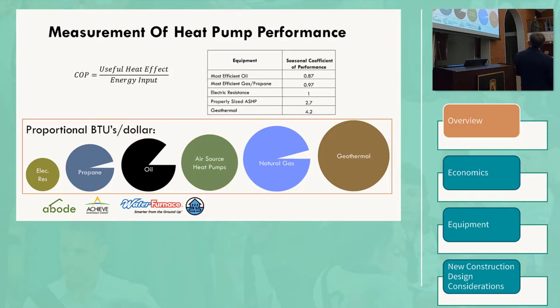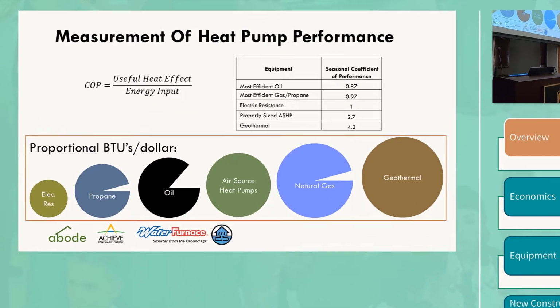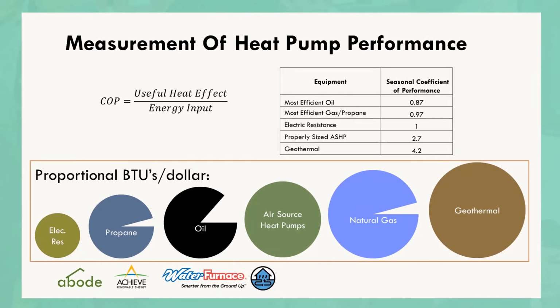Ground source heat pumps can vary based on model line and particular configuration, but the COP is typically between 3.5, or 350% efficiency, and about 6, or 600% efficiency, so somewhere in that range.